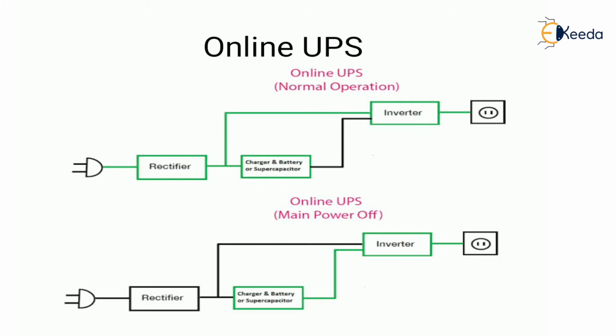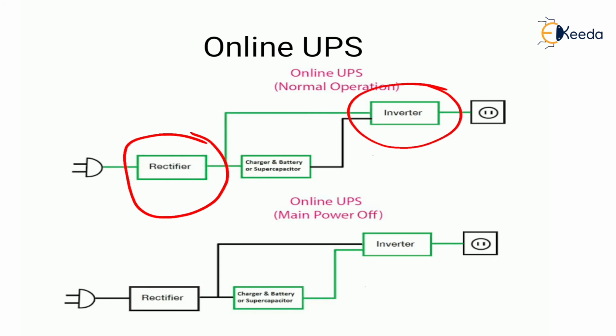Next is online UPS. This UPS provides the highest level of protection, and an online UPS absorbs the incoming AC supply, converts it to DC with the help of the rectifier, and this rectifier provides rectified output, which is then inverted to AC supply by the inverter to supply the critical load. An inverter supplies the regulated AC power to the load at all times, either from the rectified mains or from the battery.